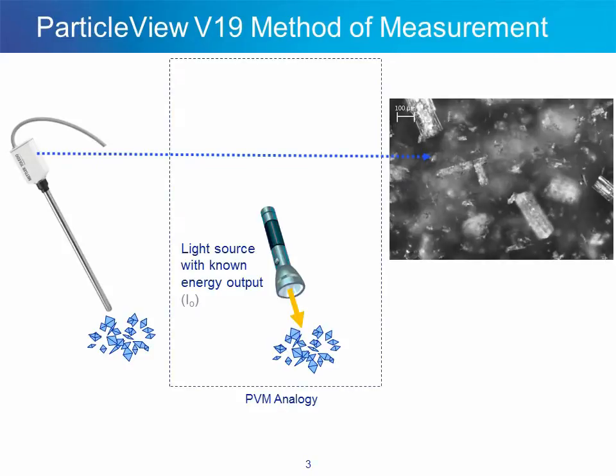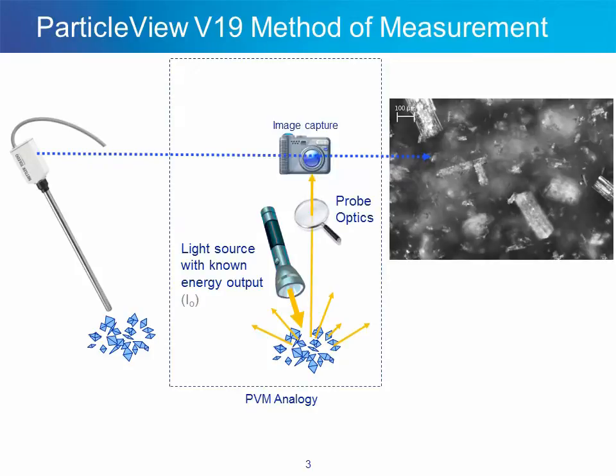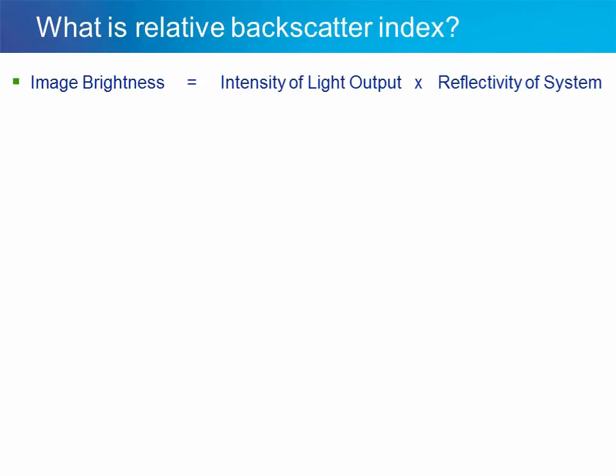An internal light source illuminates particles directly in front of the probe window. The light gets scattered back up through the probe and the probe optics, where a camera captures the image. Each image that is captured is of a known brightness — this image brightness is equal to the intensity of the light sent out through the probe multiplied by the reflectivity of the particle system.